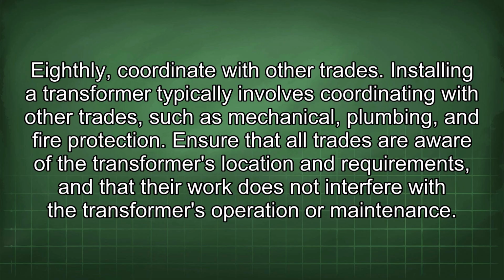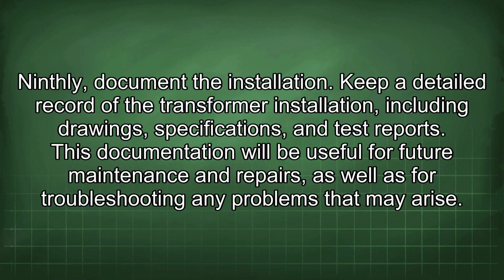Eighthly, coordinate with other trades. Installing a transformer typically involves coordinating with other trades, such as mechanical, plumbing, and fire protection. Ensure that all trades are aware of the transformer's location and requirements, and that their work does not interfere with the transformer's operation or maintenance. Ninthly, document the installation. Keep a detailed record of the transformer installation, including drawings, specifications, and test reports. This documentation will be useful for future maintenance and repairs, as well as for troubleshooting any problems that may arise.